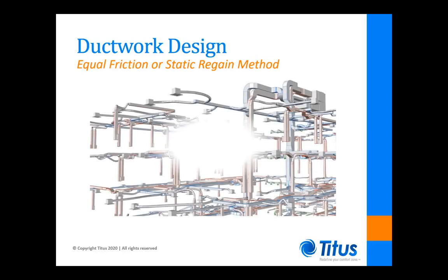One of the most important aspects of a VAV diffuser system design is the ductwork. Overall, the ductwork design requires a little more effort and care than a conventional VAV system. The duct system pressure must be controlled, as system pressures above around a quarter of an inch behind the diffusers may lead to unacceptable room noise levels. There are two common duct sizing methods used for VAV diffusers: equal friction or static regain.